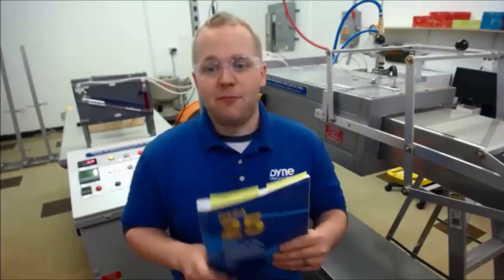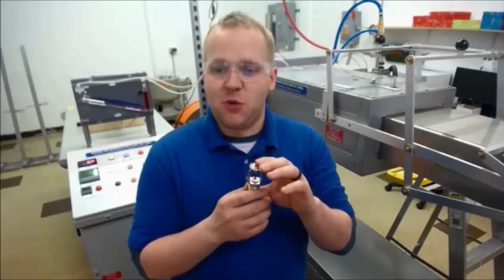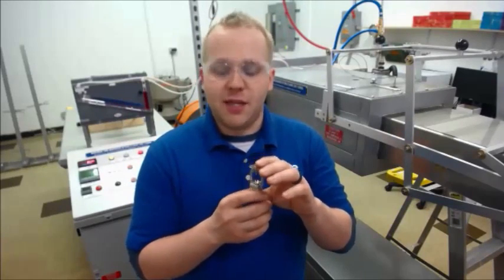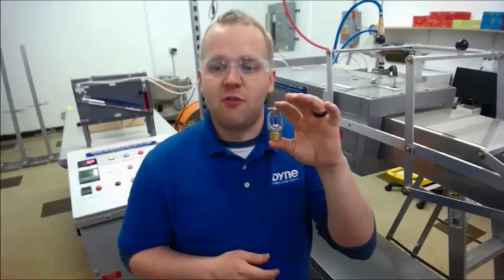This is why I'm here today. I'm going to show you sprinklers with different amounts of loading and how their response times are impacted. Today I have five sets of four prepared. The first set has no loading, the second set has very small amounts of loading, and each set after that has more and more loading. I plan on showing four of each type to demonstrate repeatability. The head we are using for all these tests is a Reliable F1 FR series head from 2016, the RA1414. It's a quick response head, 155 degrees Fahrenheit.